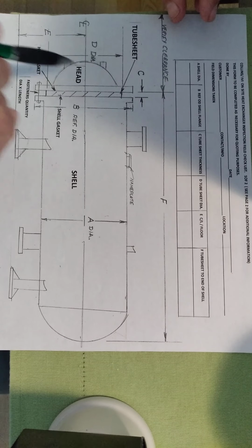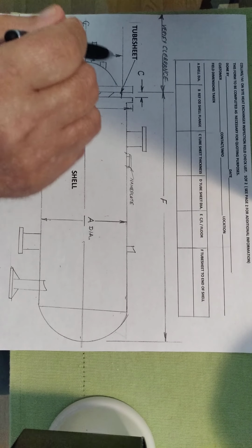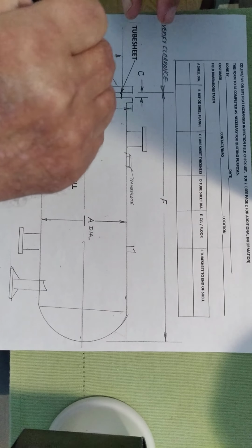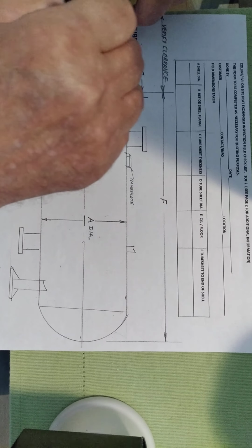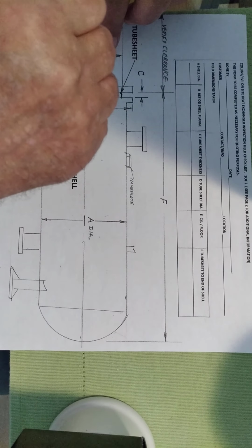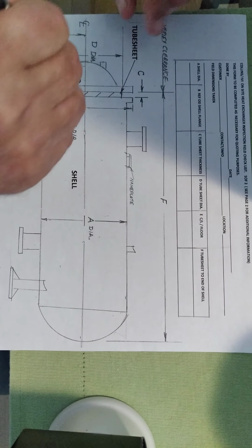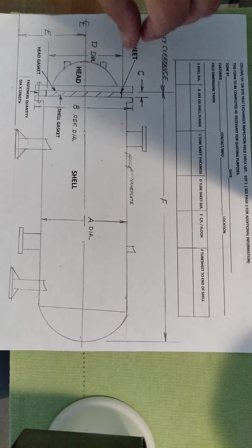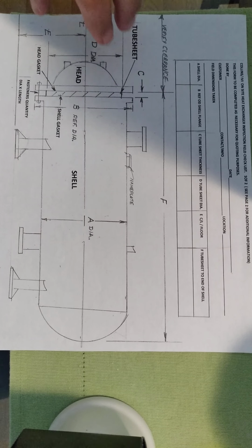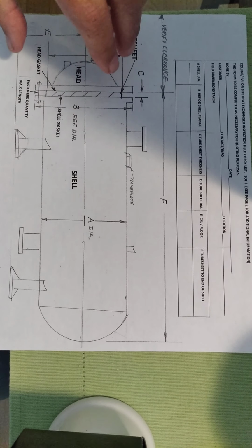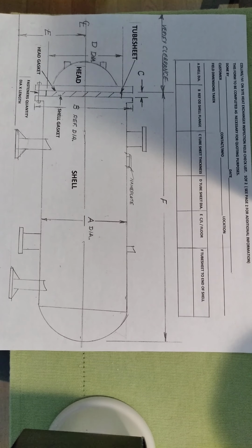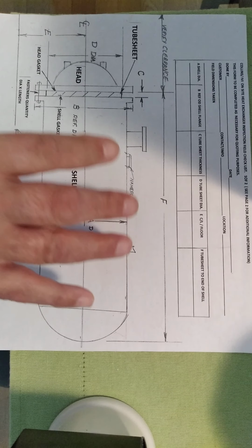And so you have to look at the situation for removing piping going to the head of the unit. There's going to be an inlet and an outlet here, and you have to look at any other piping, if they're unions, if the piping has to be replaced, if there's gasket joints on any valves or joints. You have to look at all of that in the field. If you can, take pictures, because if you think you're going to remember with everything going on, you're not. So take some photos, that always helps.